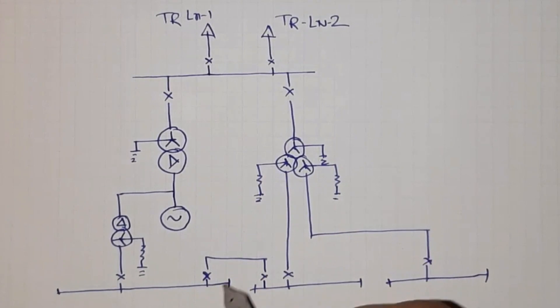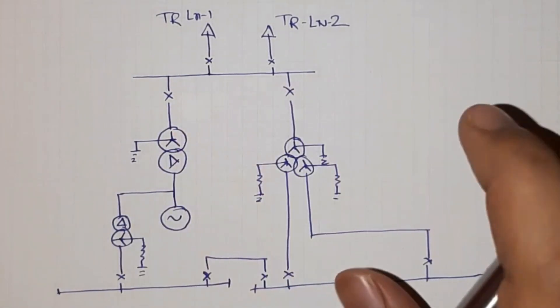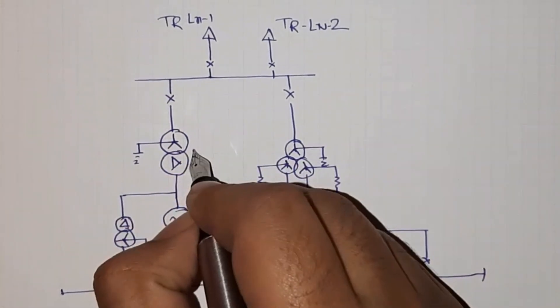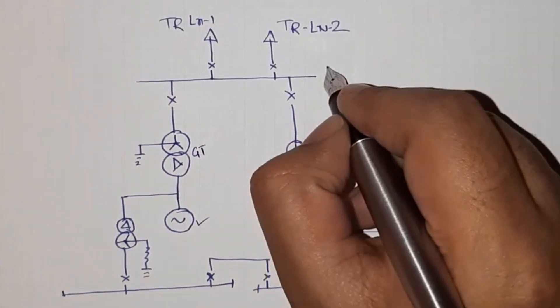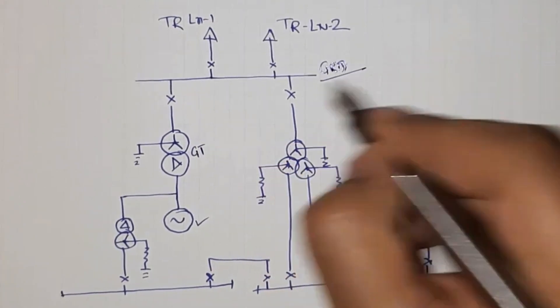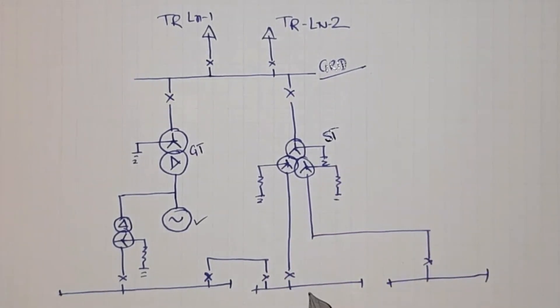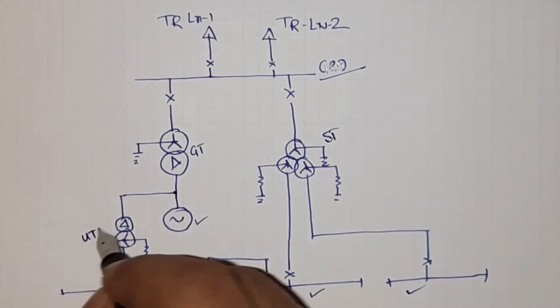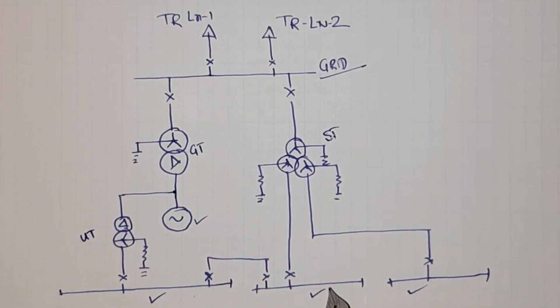I have drawn a typical picture of a power distribution of a power plant. This is the generator, this is the generator transformer connected with the generator and feeding the grid. From the grid there is a station transformer feeding the station switchboards, and from this point there is a unit transformer also connected with the generator feeding the unit switchboard. The unit switchboard and station switchboards are tied with each other.